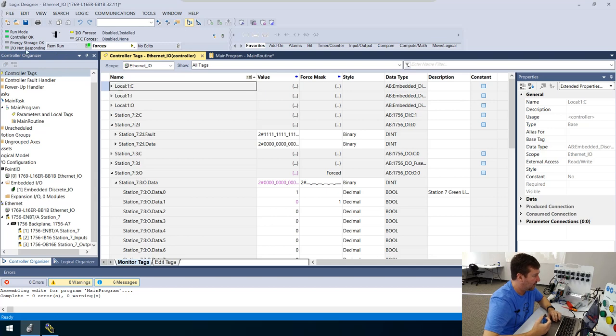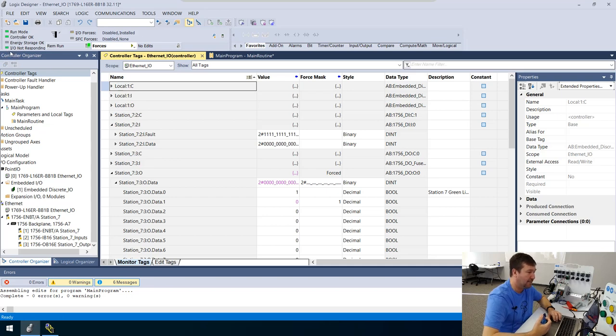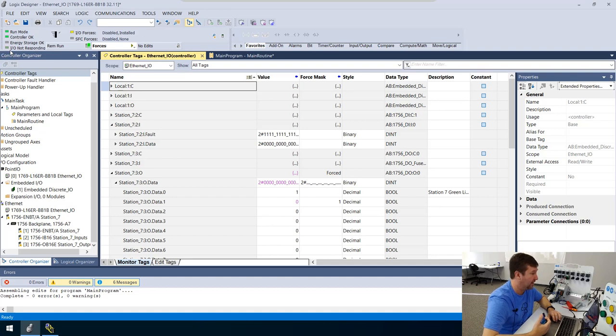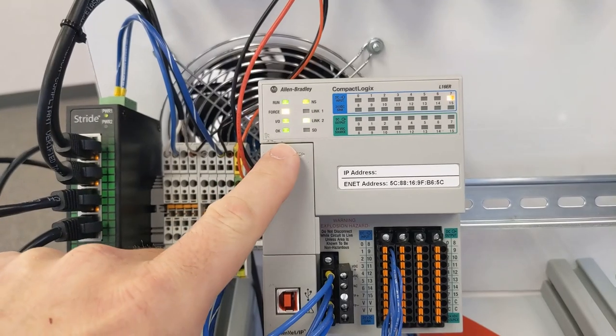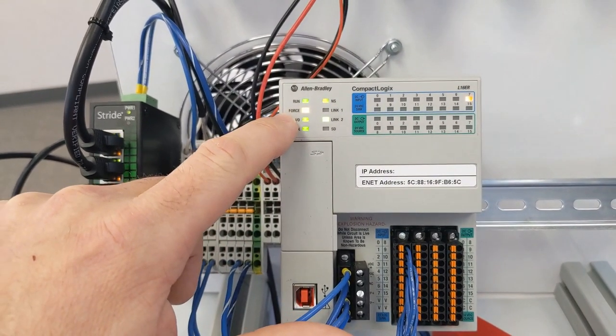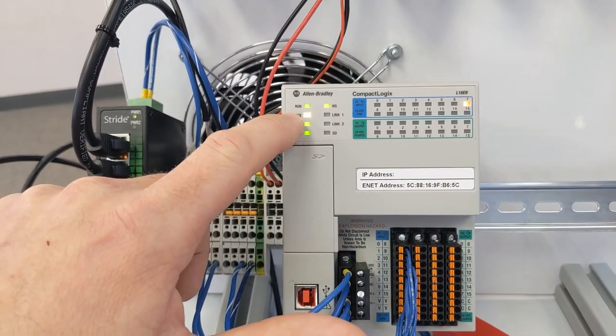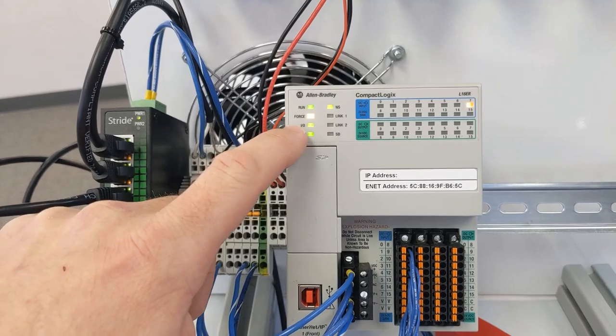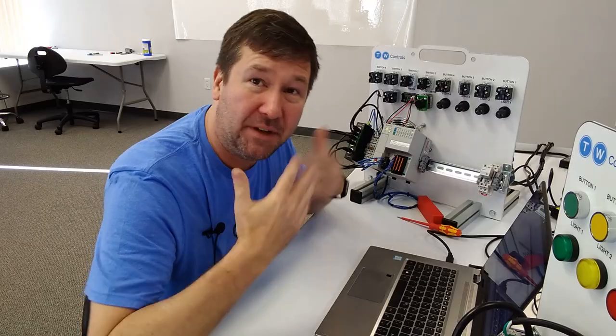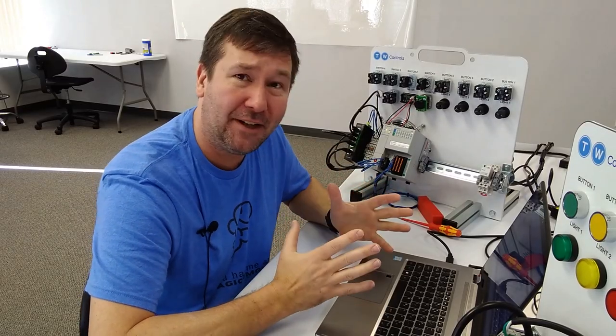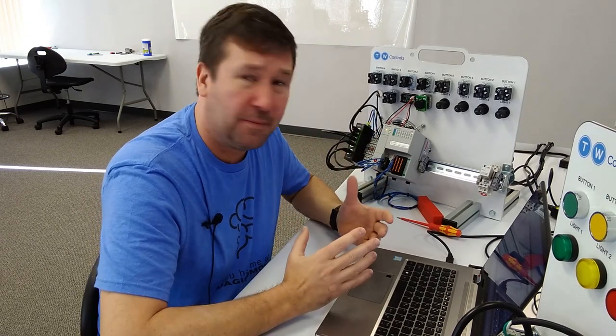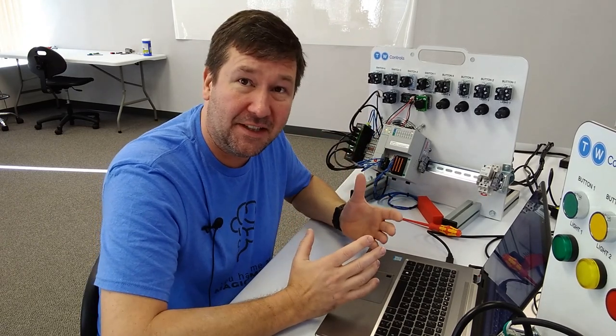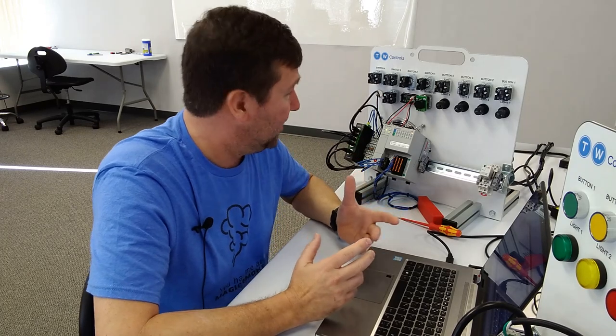So I'm in Studio 5000 and I am looking at a PLC program and I'm online. I can see that I have a solid run light. I can see that my I/O responding light is flashing and I can see that my force light is flashing. And if we look at the front of our PLC, we see a very similar situation. We have a force light flashing. We have an I/O light flashing. So we see some things matching up, but that's definitely not enough to tell us with 100% certainty that we're online with the right PLC.